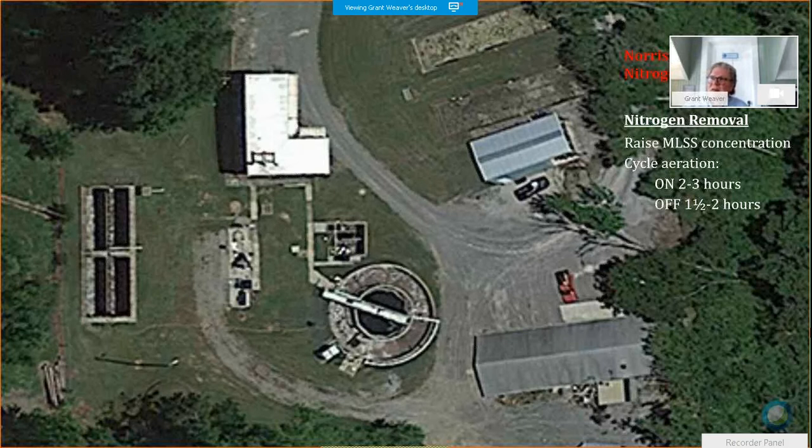I didn't check to get the latest numbers, so Tony or Doug, if one of you is listening in and you care to, you can tell us what your air on and air off cycles are, and we can share that with everybody. But they run the air on and the air off to go from oxygen rich for ammonia conversion to nitrate, to oxygen poor for nitrate conversion to nitrogen gas. And remember, the ultimate product of nitrogen removal is the nitrogen actually, instead of migrating out as part of the TSS, going into the atmosphere, which is 3/4 nitrogen gas to begin with. So I like to say it goes home to mama.